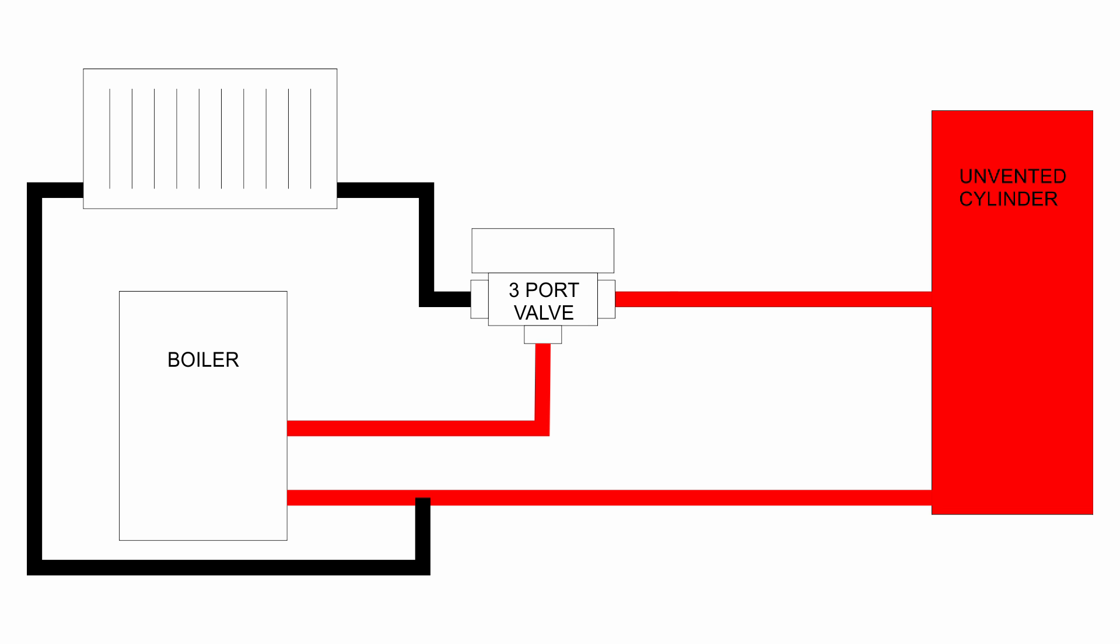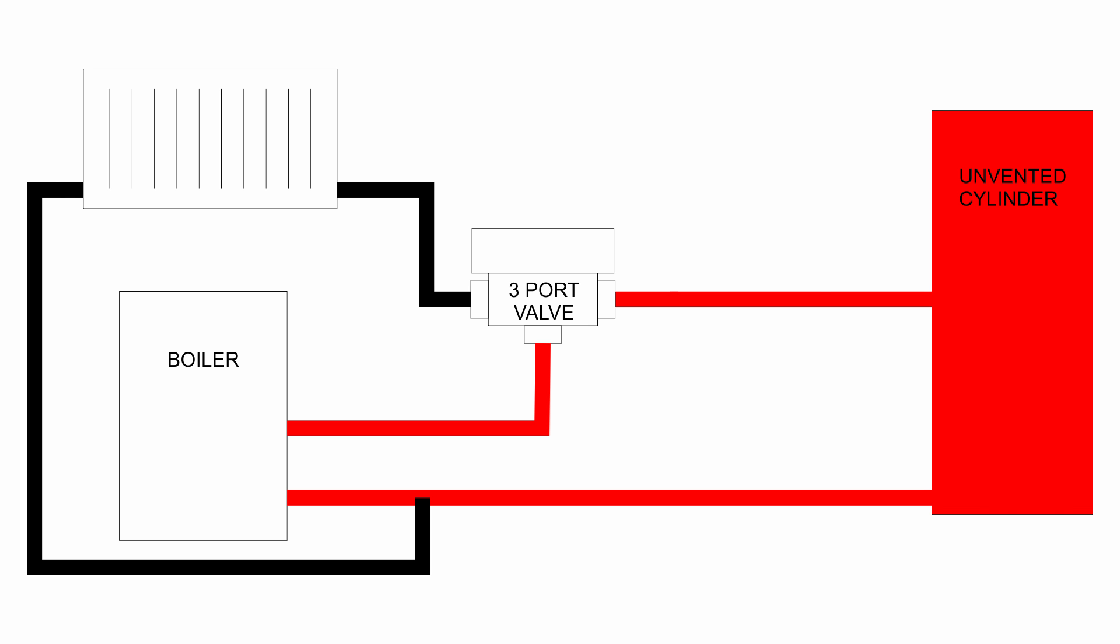So that's really the reason for putting the extra two port valve in there, so regardless of whether the boiler is working or not, cutting power to that valve will close the valve off and prevent water flowing to the cylinder, regardless of what the rest of the system is doing.